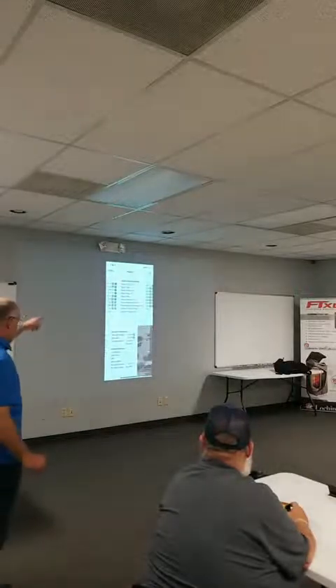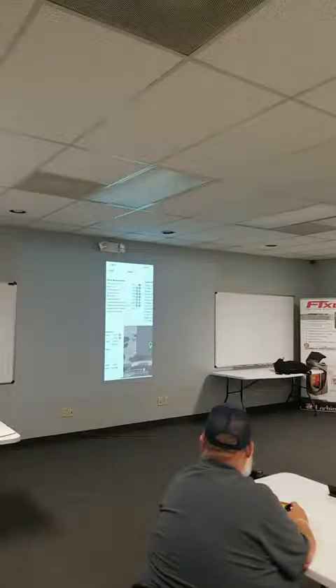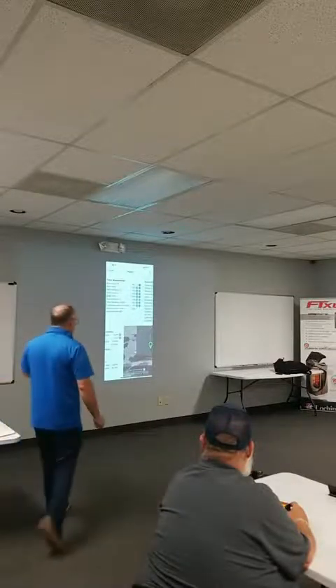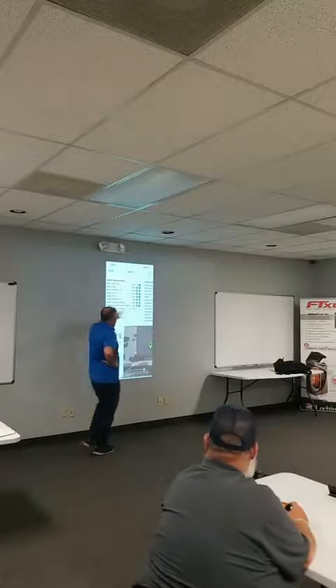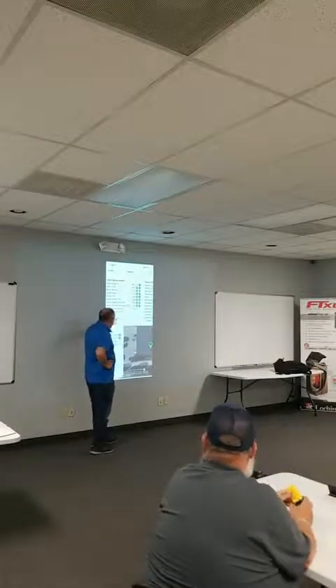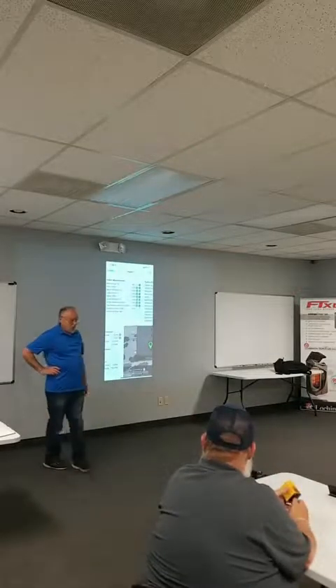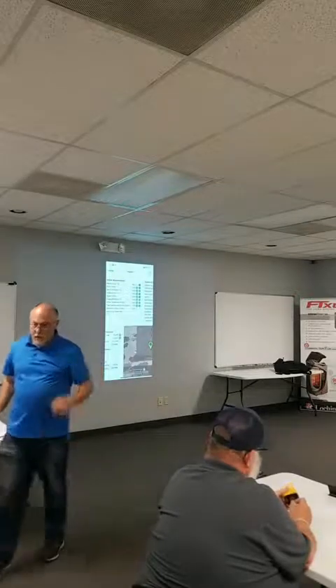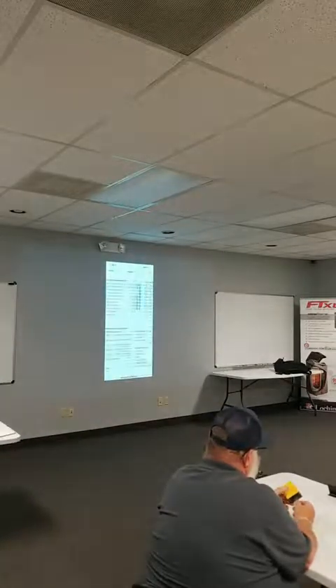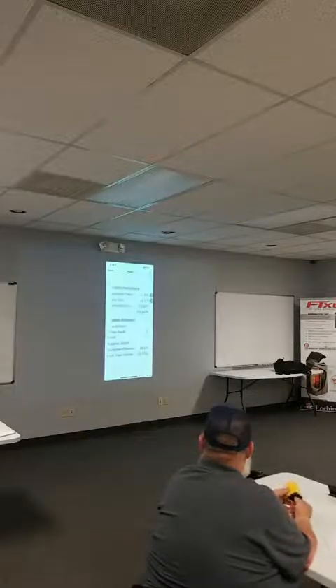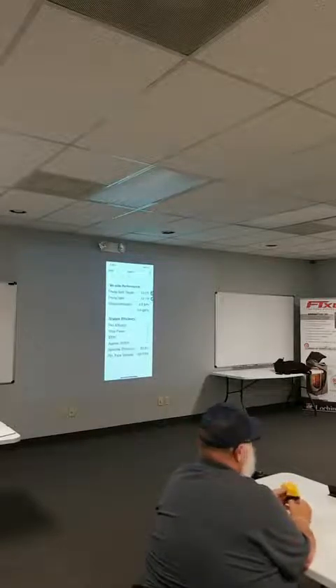Now, this one, I have range indicators on here, so it's showing what's too high and too low. Everything else got a check mark on it. These little symbols are showing us what tool the measurement came off of. So this came off of the fieldpiece probes, right? And then we've got all the different measurements in the report. This is more for the office than it is for the customer. They won't understand that stuff.